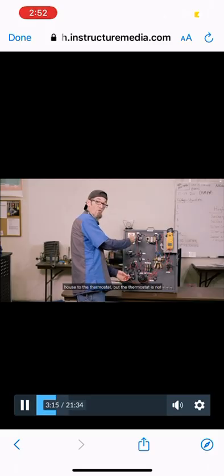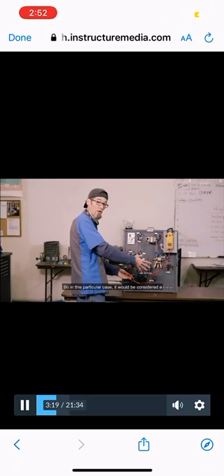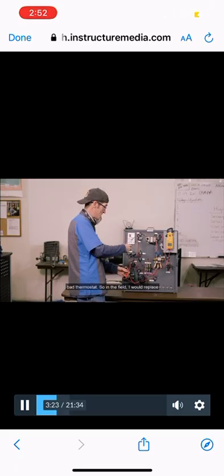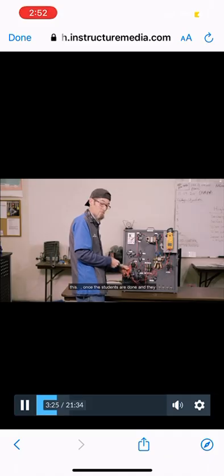So what that tells me is I have power going into the house to the thermostat, but the thermostat is not actually sending it back up to the unit to turn it on. So in this particular case, it would be considered a bad thermostat. So in the field, I would replace this. Okay?